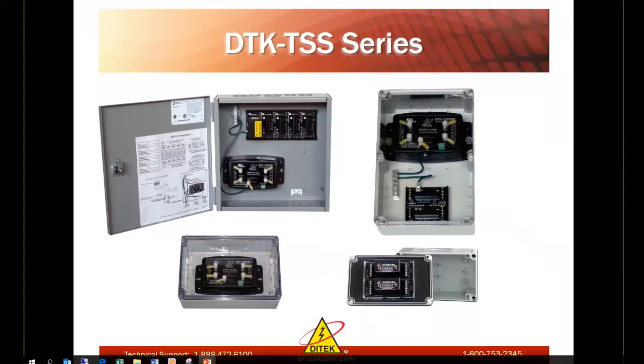You can basically plug in any value of our modular devices, as well as the phone line protector and the F or B series. The next one over to the right is the TSS2, for smaller applications, utilizing the 120SRD and the NEMA enclosure, and the 2MB, which protects up to 4 pair, if you will. As you notice on the TSS1 and the TSS2, we offer the ground bus that gives you a reference to ground. So we ground all our surge protection internally in that box. The only ground that you have to pull in is the one for the 120SRD. Everything references back to the electrical service ground.